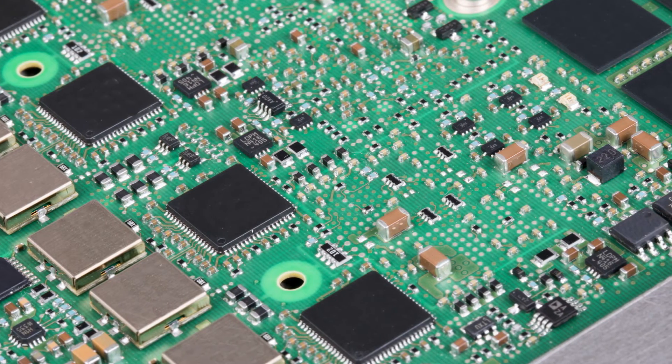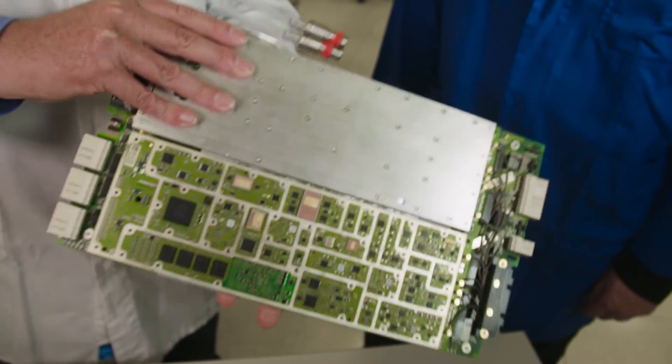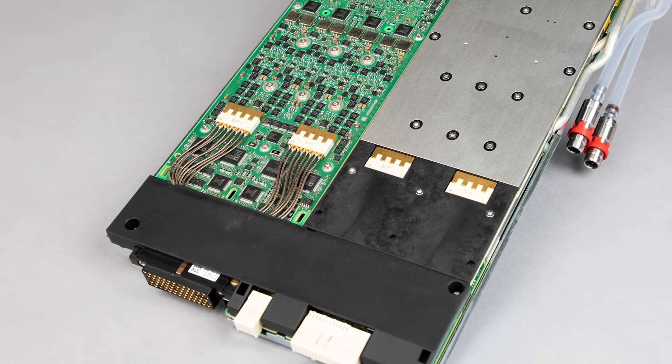The spectrum of the IoT world is very diverse, and so are the analog signals found there — ranging from DC over audio to high-speed baseband interfaces. WaveScale MX is the only solution on the market that offers 32 fully independent instruments with source and measure capability behind each pogo pin for highest flexibility, throughput, and parallelism. WaveScale MX is also very easy to use: all you have to do is specify the sequence and characteristics of your test signals, and the software selects the most optimal settings.